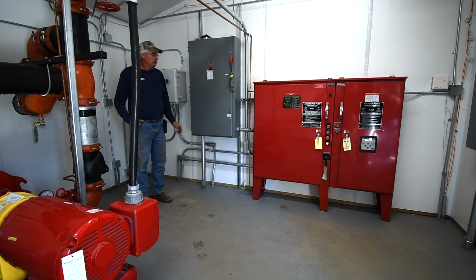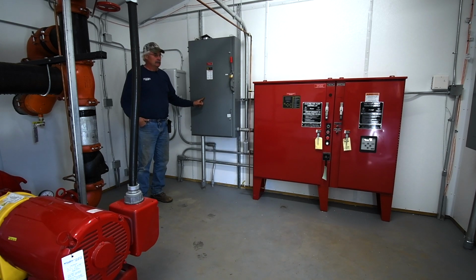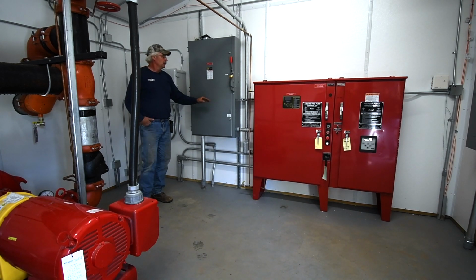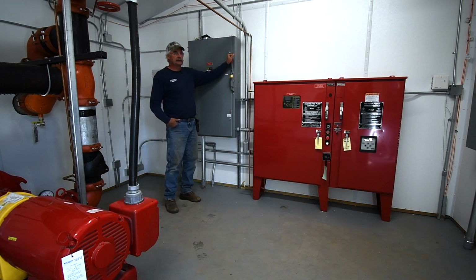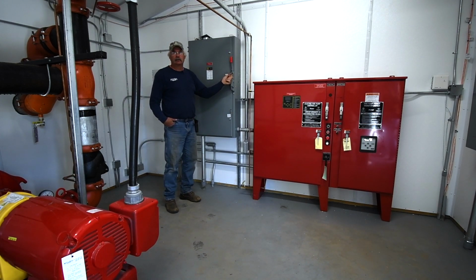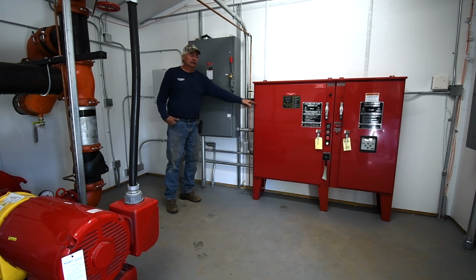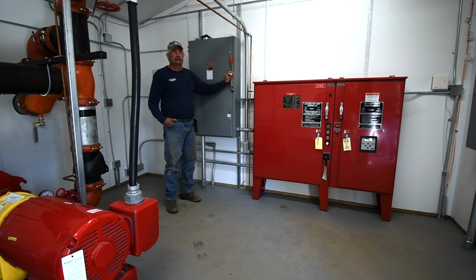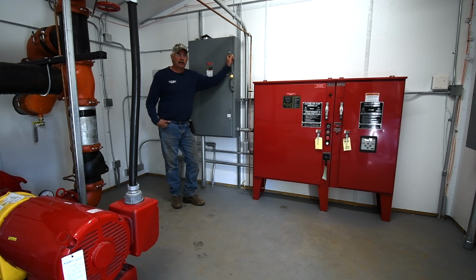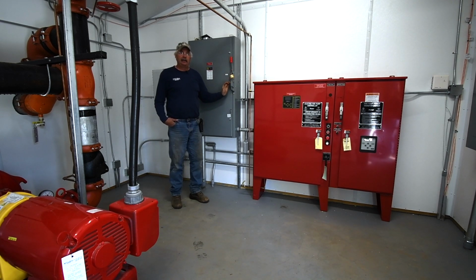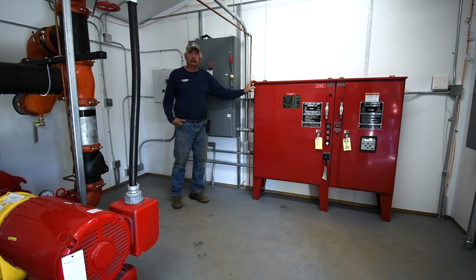Main disconnect for fire pump controllers. This cabinet's always live, the lever's up, locked in, locked on. So at any time, working on this controller, this would have to be unlocked, shut the power off, and tagged out to make sure before working in a high voltage cabinet. You have to get a hold of the property authority, like Ben Bowstring, to come in and unlock this for you and put a lockout, tagout on it before you do any work on the inside of this cabinet.